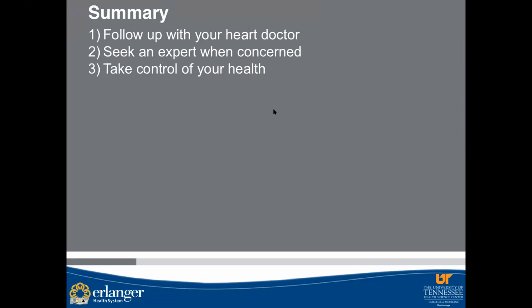But actually, the more a pacemaker or defibrillator needs to be used, the more the battery will be drained. So that's important. In your case, if you have a pacemaker that was put in for what we call complete heart block, meaning there's no transmission of electrical signal normally from the top chamber, and you're dependent on the pacemaker, it works all the time, then that pacemaker will drain faster than someone who only uses it intermittently, but they both need pacemakers.